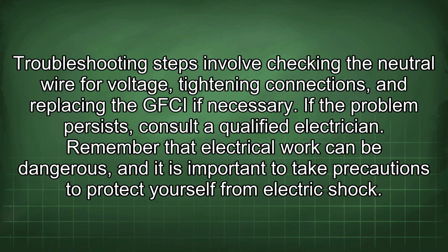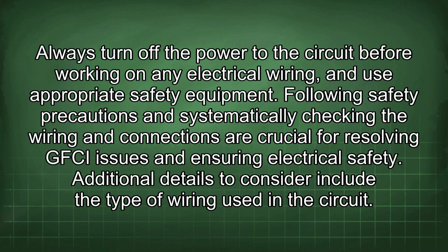Troubleshooting steps involve checking the neutral wire for voltage, tightening connections, and replacing the GFCI if necessary. If the problem persists, consult a qualified electrician. Remember that electrical work can be dangerous, and it is important to take precautions to protect yourself from electric shock. Always turn off the power to the circuit before working on any electrical wiring, and use appropriate safety equipment. Following safety precautions and systematically checking the wiring and connections are crucial for resolving GFCI issues and ensuring electrical safety.